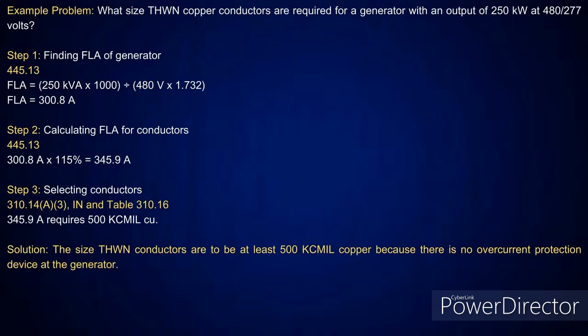Now, when you go look at 445.13, it says when you're doing the conductors for sizing the generator, you're going to take it at 115%. Okay? Right. And that's going to give you 345.9 amps. I go look at table 310.16. The next size above that's a 500 kcmil.